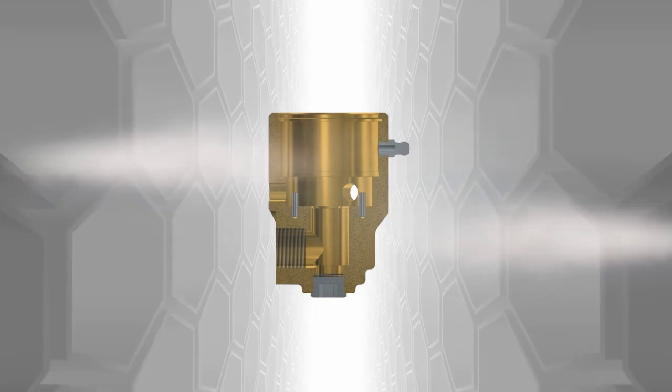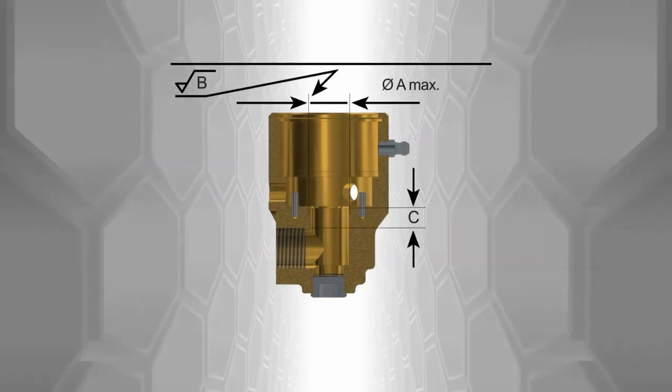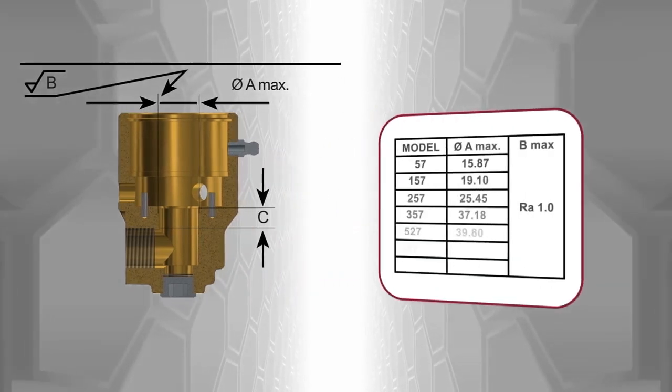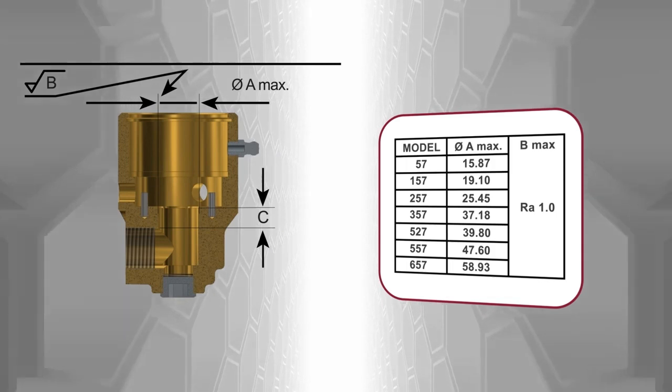Clean the union housing thoroughly then measure the bore surface for wear or pitting. The measured value should not exceed the maximum value given in the table for your 57 series model number.